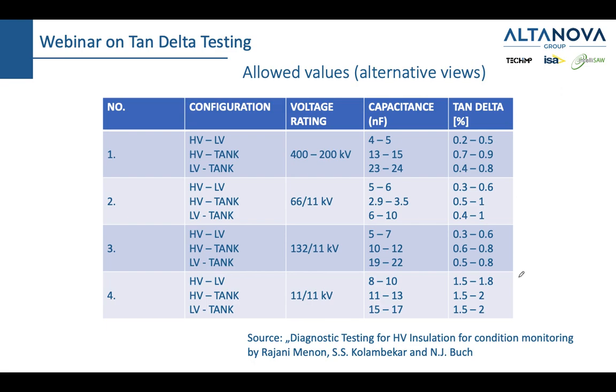But in preparation for this webinar, I went through some articles, and there was an interesting article. This is an article which was made by Mr. Rajani Menon and his collaborators. Here, you actually have four, let's say, categories. We talk about extra high voltage transformers, and then medium voltage transformers, and then again some high voltage transformers, and then some standard distribution transformers. So why have they done this? Because it is not always the same whether you have a weak insulation at 400 kilovolts or weak insulation at 10 kilovolts. Of course, if you have a weak insulation at 400 kilovolts, it's a bigger risk than having a weak insulation at 10 kilovolts.